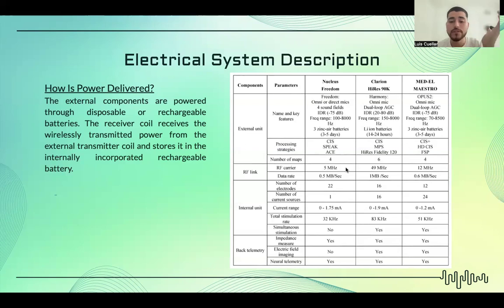The current range is also 0 to 1.75 milliamps. On the other end of the spectrum, we have the Med-El Maestro, which has only 12 electrodes, 24 current sources, and 0.0 to 1.2 milliamps. Okay, so this talks a little bit about the electrical system description of the cochlear implant.